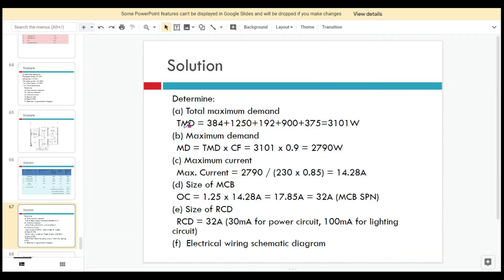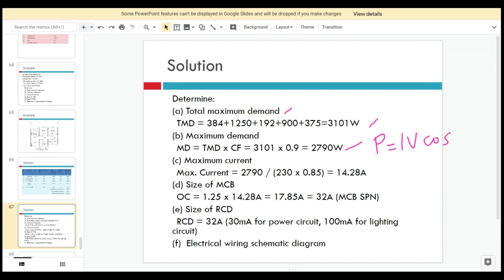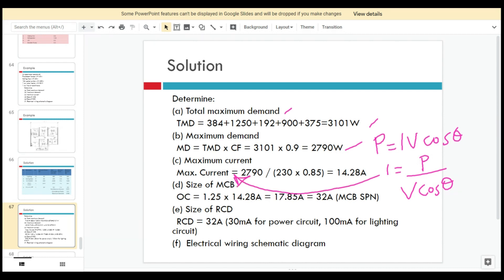This detail shows how to calculate the total maximum demand and then the maximum demand. To find the maximum current, since this is single phase, use the equation P = IV cos θ, so I = P / (V cos θ). From the maximum current, you can determine the current rating of the MCB. Using the factor 1.25 times the maximum current gives approximately 17.85 amps, so we can use a 32-amp single-phase MCB.